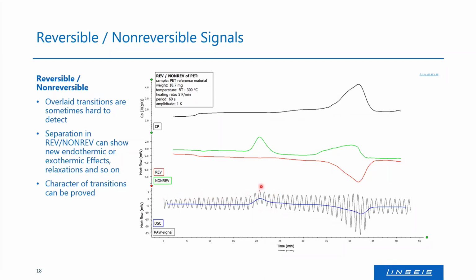So the curves we could receive. At first, of course, the CP, the non-reversing. And here it's interesting. What you can see here at the beginning, in the range of the glass transition, is a pretty small endothermic peak. And this is the relaxation. Now it's possible to evaluate this transition easily, so you can see, okay, it's just a peak. And it's much easier than before with the raw DSC signal you can see here in the blue curve. Of course, you have to zoom in if you want to evaluate. This is just the scaling of my diagram.